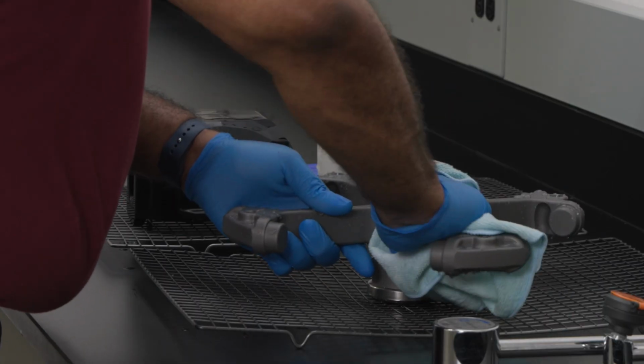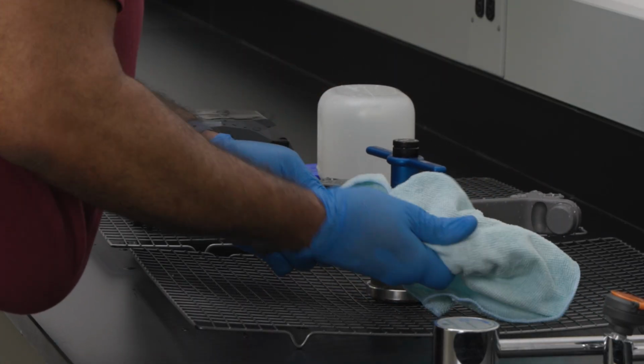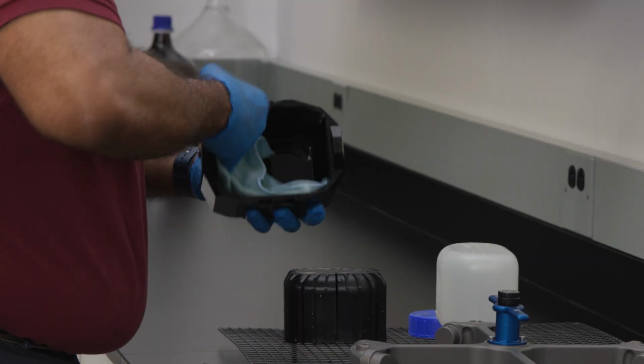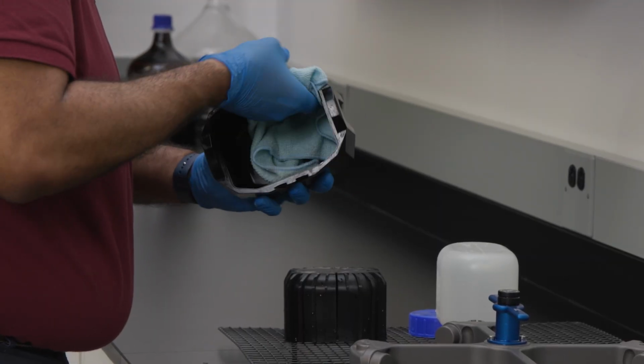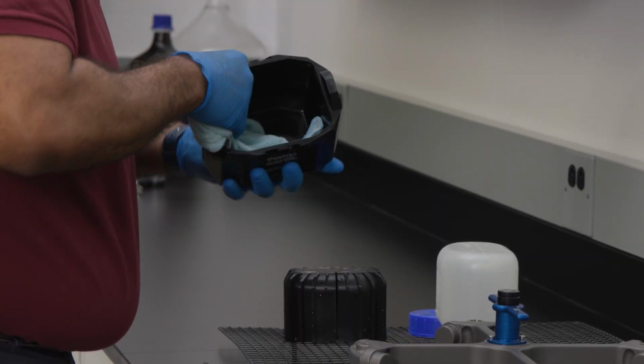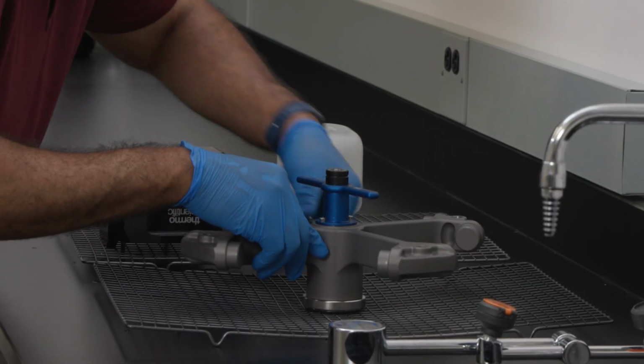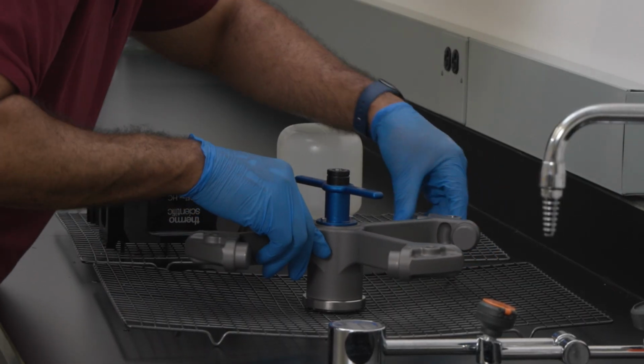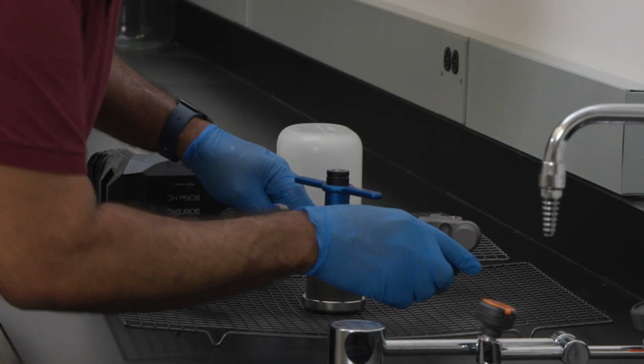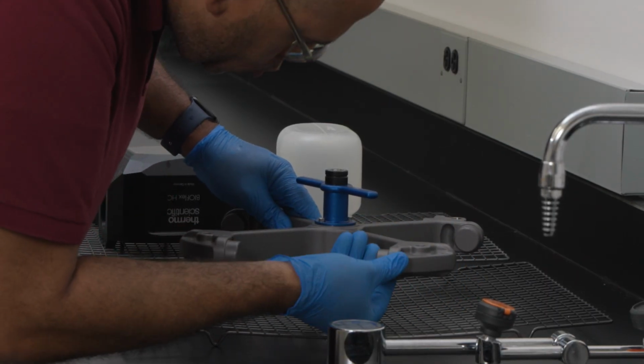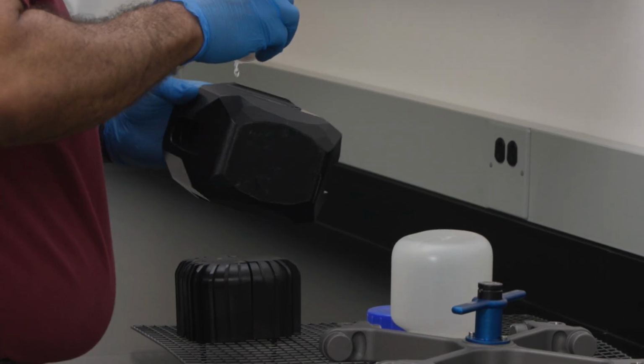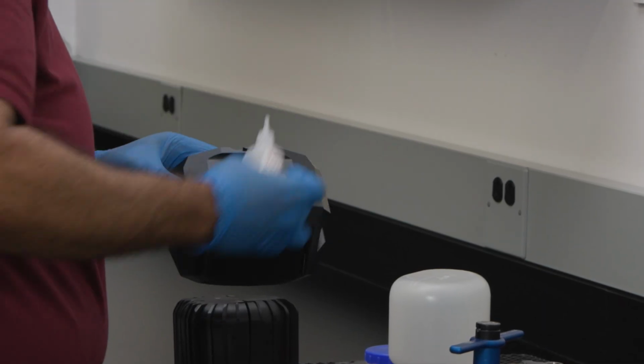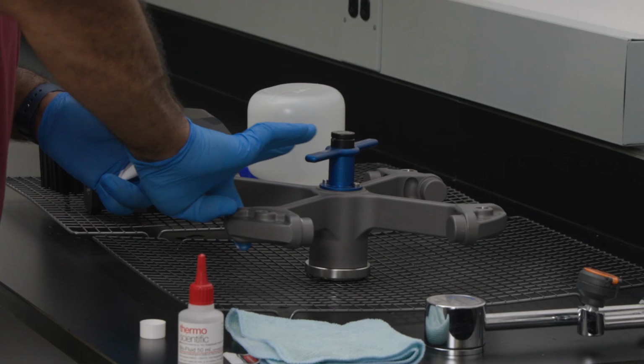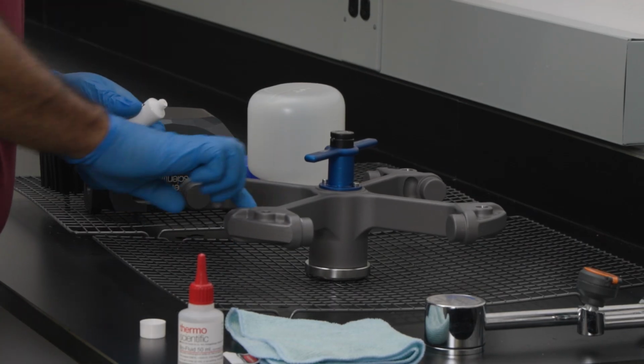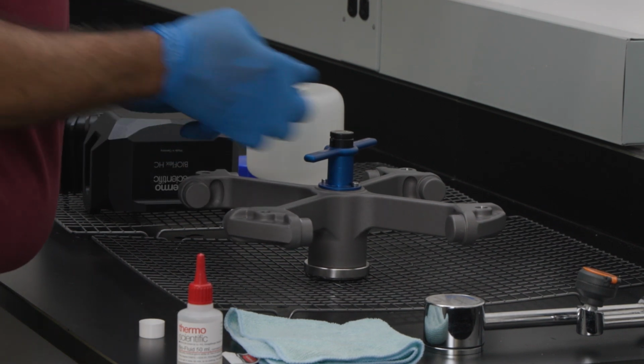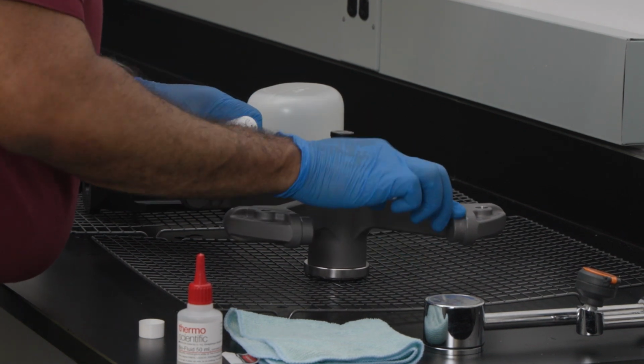After cleaning, dry the rotors and accessories with a cloth or in a warm air cabinet. If you're using drying boxes, the temperature must not exceed 50 degrees Celsius. After drying, inspect for damage, such as stress lines, corrosion, or dents. Do not use the rotor if you observe any damage. Then, treat aluminum parts and cavities with corrosion protection oil. If necessary, treat the swinging bucket rotor bolts with bolt grease to ensure the buckets swing freely.